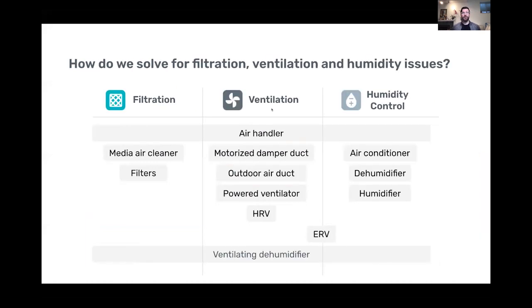So how do we solve for these 3 pillars of filtration, ventilation, and humidity issues? The first, on the filtration side, obviously filters, media air cleaners, cabinets. The deeper filter is typically a better solution because it will last longer without needing to be changed, has a higher surface area, so it's going to capture more particulates, and you can go up to a higher MERV rating to have a more efficient capture. We also see that gasketing and having a good cabinet is key to good filtration, and that typically would get installed on the air handler.